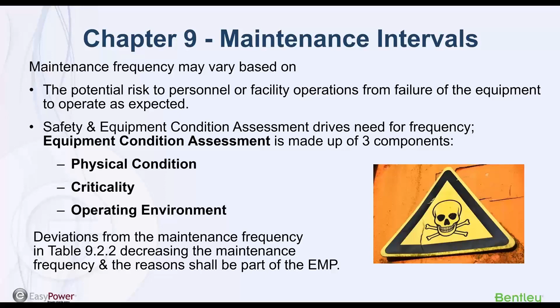Conditions of maintenance are defined in the standard - maybe a little general, vague, or ambiguous, but they do have definitions. There's a series of terms used: serviceable, limited service, and non-serviceable. Serviceable means the equipment is in good condition. Limited service means everything isn't exactly as one would wish, but it's good enough for the moment, and there are things you can do. If it's non-serviceable, that's an issue - normal operations and normal maintenance activities may have to change because non-serviceable equipment presents a significant risk. Chapter 9 provides detail about this.